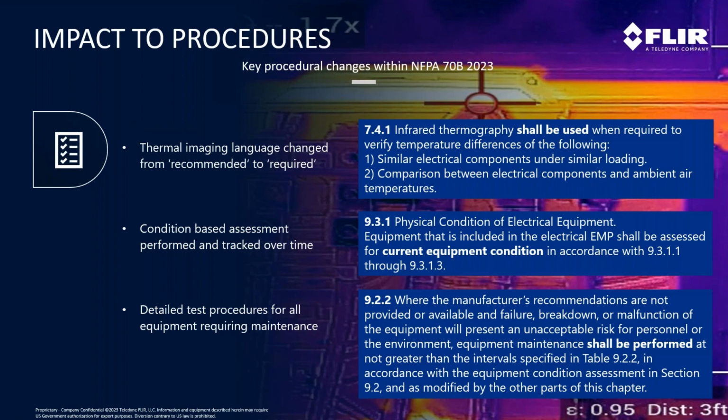I'm going to read a little bit, but where manufacturers' recommendations are not provided, there's an entire interval table that is provided by NFPA, as well as the specific tasks that need to happen from a maintenance and inspection perspective, and the frequencies that those need to happen. So if you don't have manufacturer information or those recommendations are not in place, NFPA does have some really good guidance there to walk you through the specifics of what it is that needs to be done to maintain and perform all those test procedures throughout.